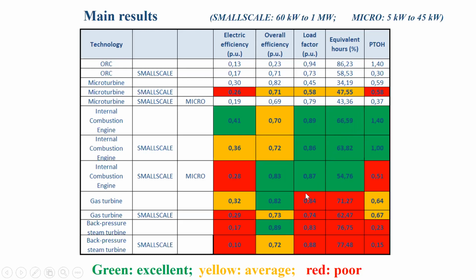Whilst in the case of gas turbines, the load factor is associated with a much higher number of equivalent hours. So life has been much easier for gas turbines, and in spite of this, the load factor is low. Engines, even if used for fewer hours, with more starts and stops, in spite of this had a very high load factor. So load factor always has to be assessed together with equivalent hours.